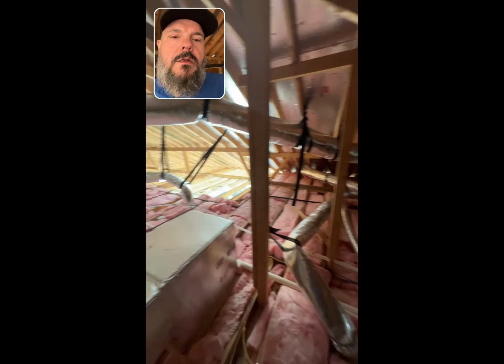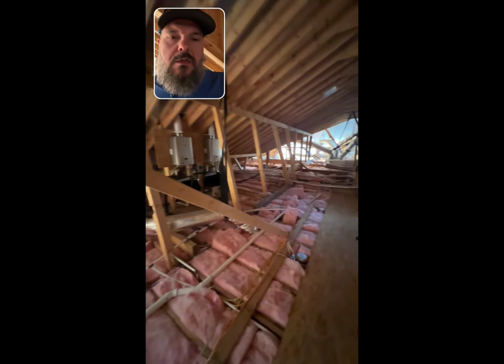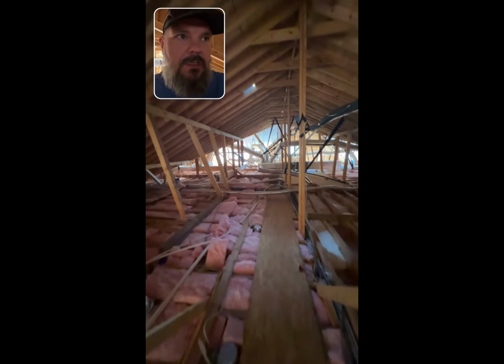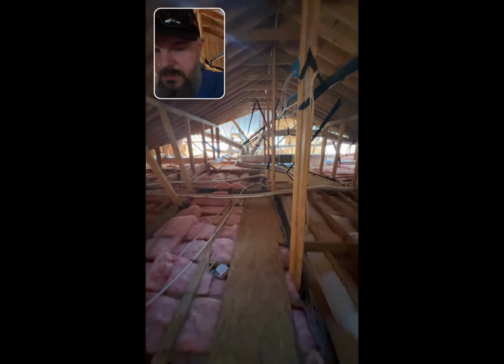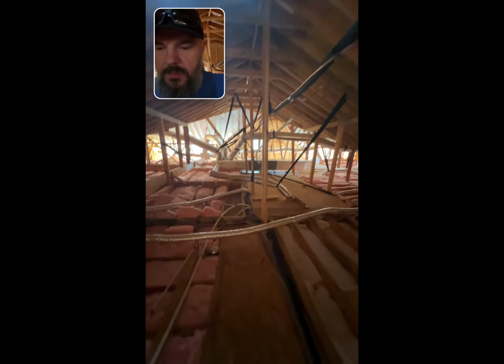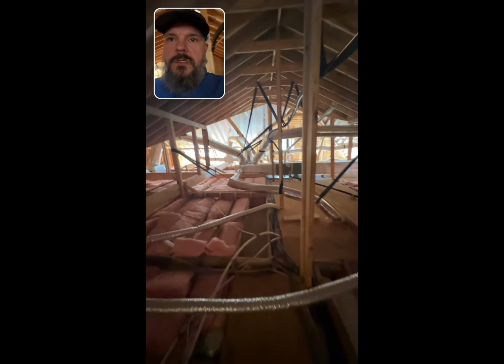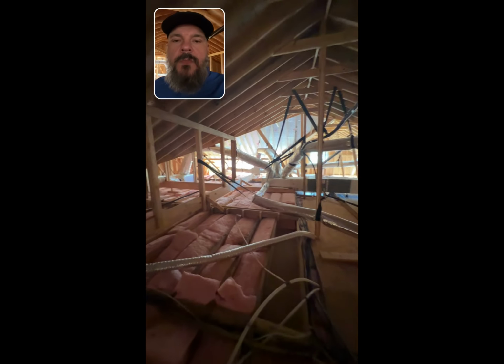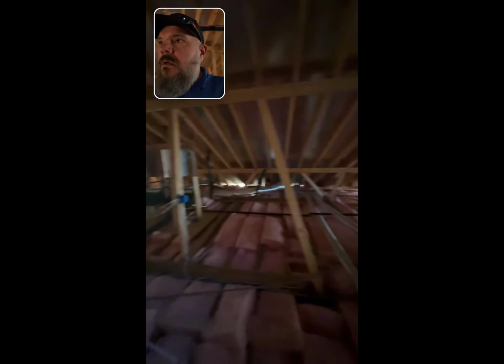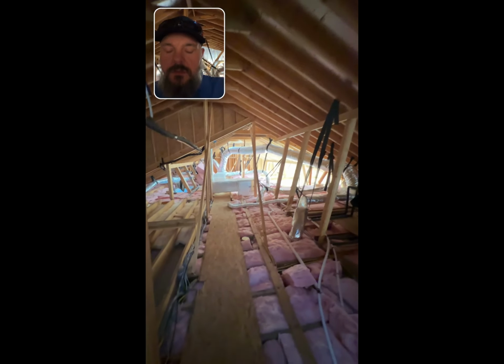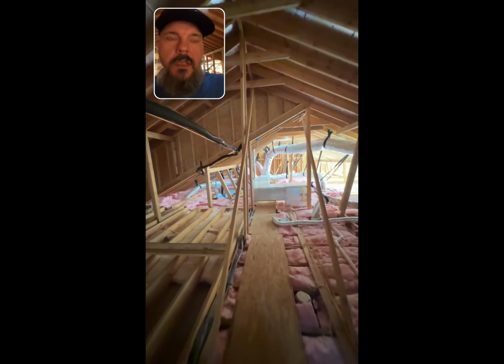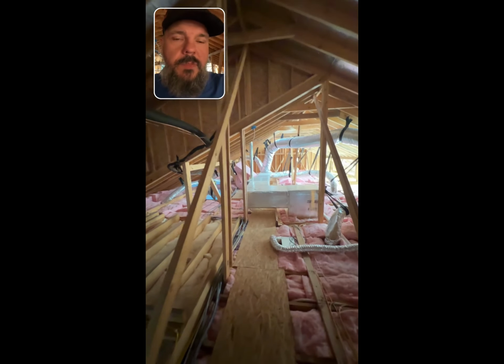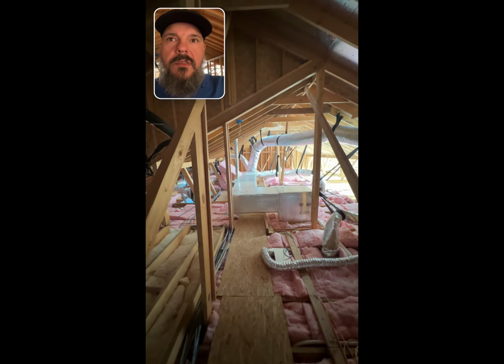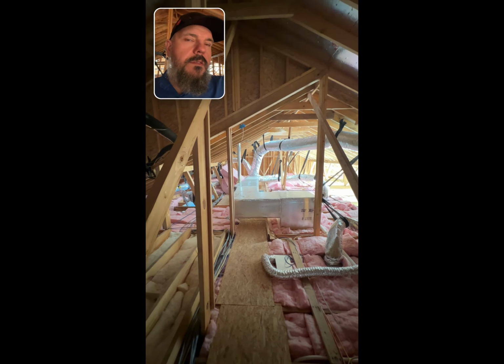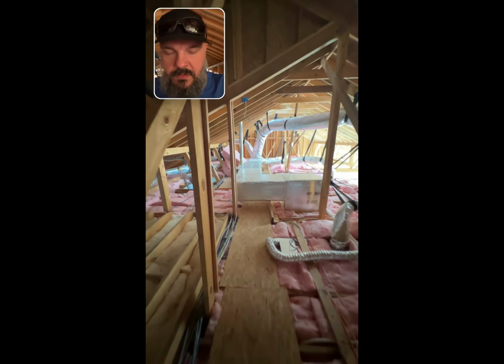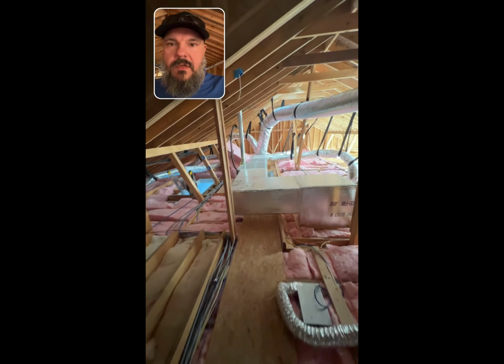First, we're in a vented attic with all of our AC equipment up here. This is the most inhospitable environment in the house, and we install the most sensitive piece of equipment up here and wonder why we have condensation issues, moisture issues, and microbial growth issues. And then take that a step further. We have the cheapest bidder doing our mechanicals, which I can tell you from experience does not get properly designed. It's installed very poorly. It's never commissioned properly, and it's hardly ever maintained.